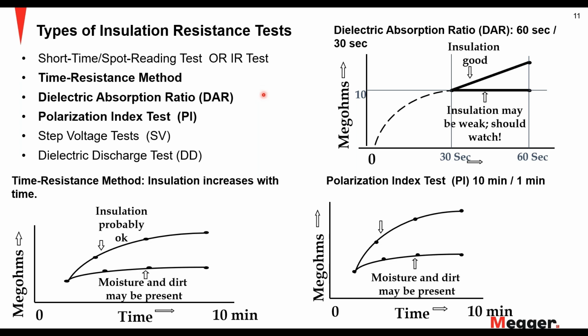Then you have your DAR, or dielectric absorption ratio. That is your ratio of 60 seconds to your 30-second reading. So the instrument takes one reading at 30 seconds, then another one at 60 seconds, and it gives you a ratio about that. Polarization index, this you will see a lot in transformers. We always do a PI test on the transformers. So it's your 10-minute reading to your 1-minute reading, similar to a DAR, but just time is different, 10 minute to 1 minute rather than 30 seconds to 60 seconds.